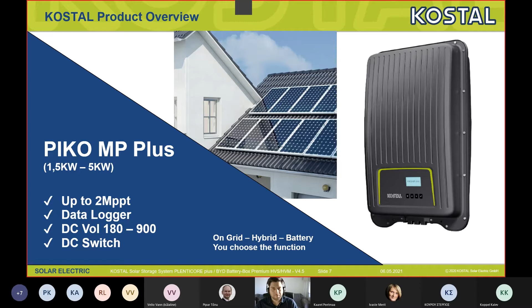Let's distinguish a bit between the battery capability and the hybrid capability. On the left side, we have the PIKO MP Plus inverters with 1 MPPT tracker, so you can use it as a pure PV inverter. You can connect only DC modules to the DC input of the inverter, and self-consume the energy that you are producing.